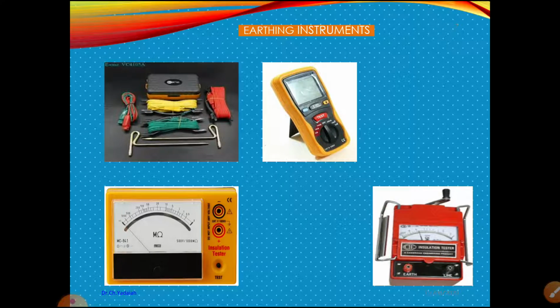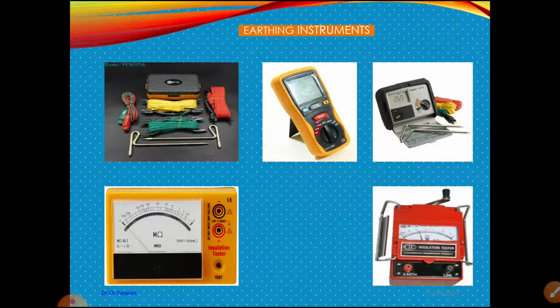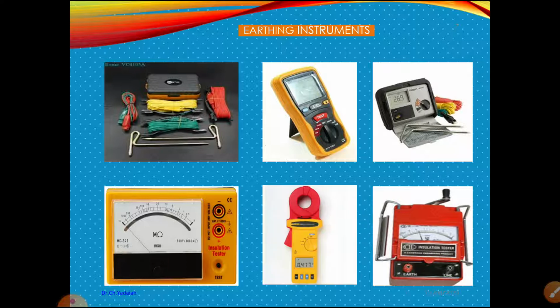Now we can see the probes, three rods, and we measure based on the distance between them. You can see this one and another type of earth resistance meter. These are all used to test how much earth resistance we have, and to maintain the minimum earth resistance. Sometimes we can also use a clamp meter to measure the earth resistance.